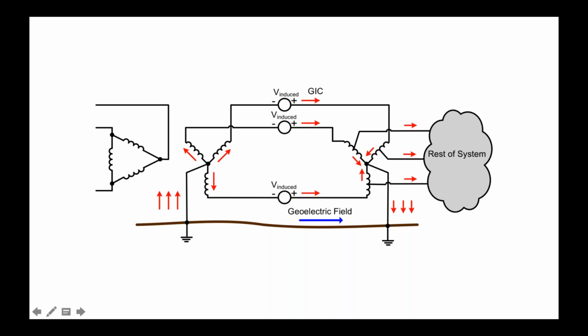What happens during a magnetic storm is that the magnetic activity induces a quasi-steady, quasi-DC geoelectric field in the interior of the Earth. I say quasi-steady because it varies slowly in comparison to the rather rapid variations that an electric power grid system has, typically at 50 or 60 hertz. So that induction of a geoelectric field in the Earth's electrically conducting interior, represented there by this geoelectric field vector, can find its way into the electric power grid system via the grounding connections.